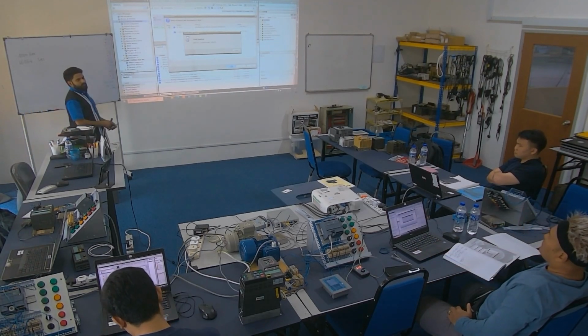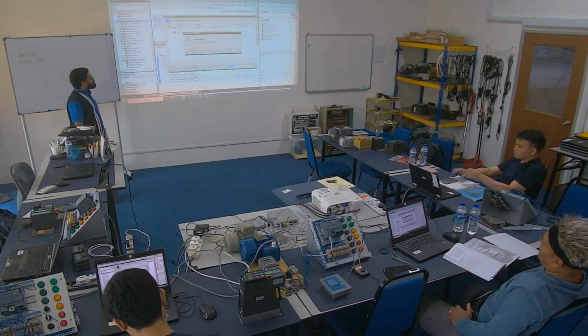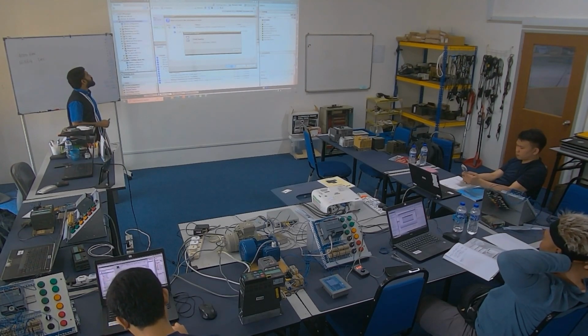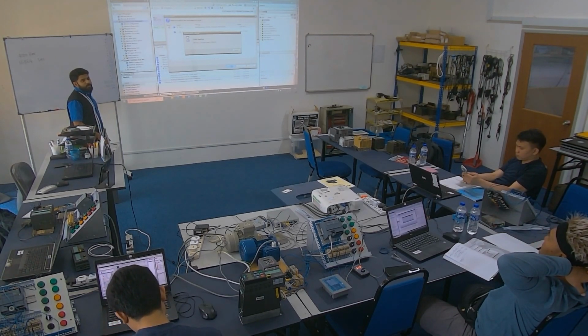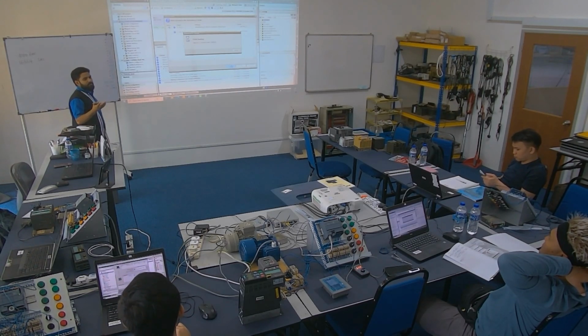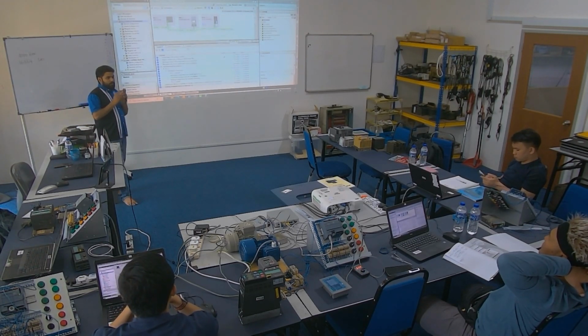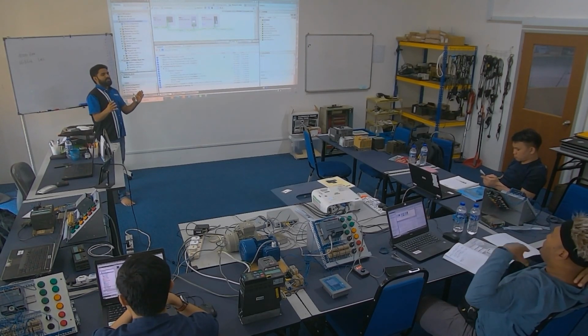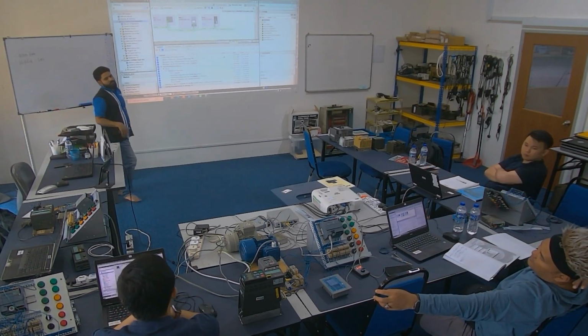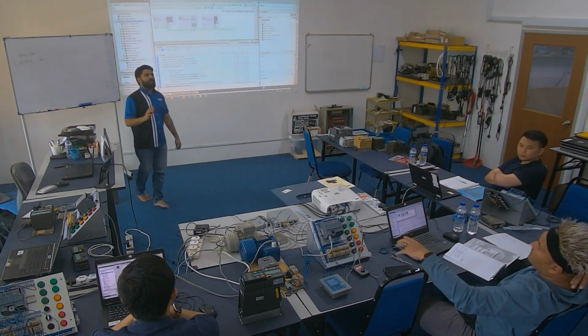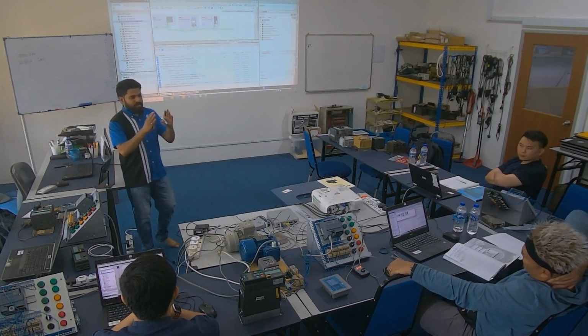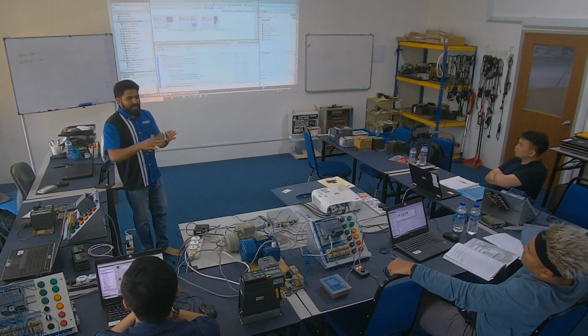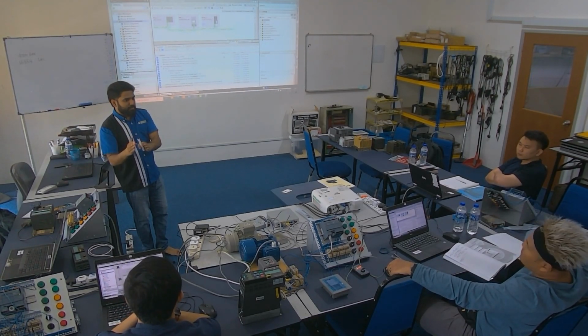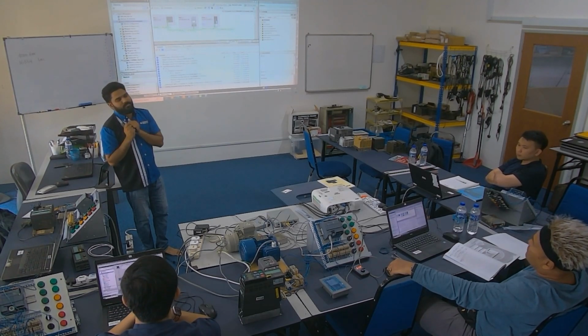It takes a while, because it's downloading your configuration — all your settings, the drive setting, the PLC setting, the IP address, everything will be downloaded to the PLC. But we didn't program anything, because what we downloaded was only the hardware. The program is considered software. So what we downloaded just now is telling the PLC: this is my drive, this is my drive part number, this is my drive IP address, everything.